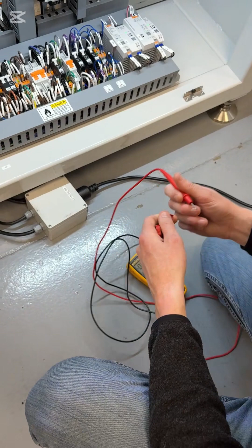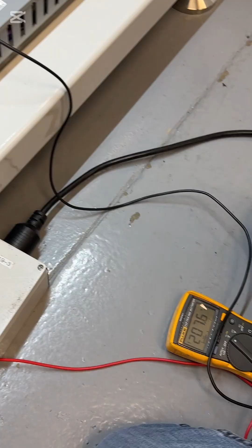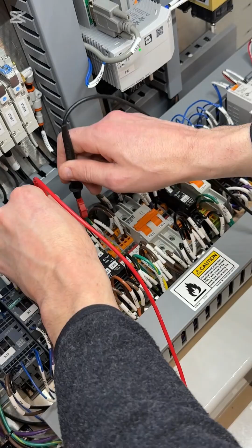You'll have 208 AC right here, same with CV5 and CV6. So if you test the output, it should read 208, 210. Same deal here, you should also have 208, 209. As you move over here, you'll start to see that you get lower voltages.